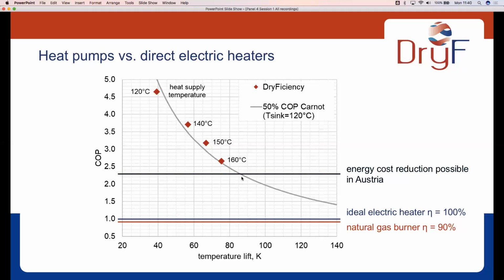But if we only look at the end energy savings, there is far more potential to use the heat pump, because the threshold when the heat pump does not allow for energy savings compared to an electric heater is given here in blue. So there's a huge lift possible. And if we compare it to the natural gas burner, that's the red line. And it also shows that in this temperature range given here, the heat pump always allows for end energy reductions.